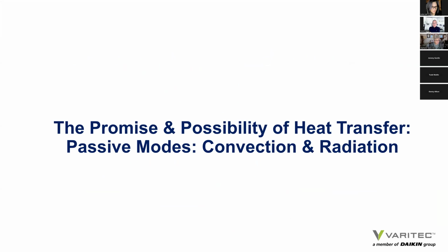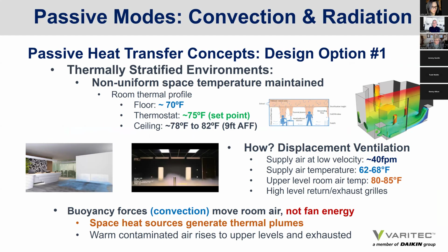So the promise and possibility of heat transfer. We're pretty aware of the mechanically driven heat transfer modes of conduction and evaporation. What about the passive modes in a HVAC design, convection and radiation? Well, first of all, passive heat transfer can occur by creating thermally stratified environments in a building or in a space. Instead of maintaining a mixed air uniform temperature throughout the cubic volume of space of plus or minus 2 degrees, we actually let the space be stratified.